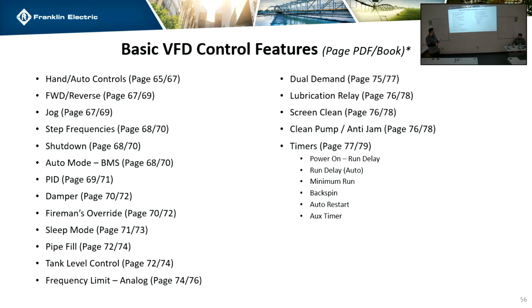73. If I heard that right, if the drive fails for whatever reason, instead of using the drive, it'll automatically change over to bypass. Yep. So if you don't trust the drive or you want it to be across the line, you can also have the drive, instead of running itself, just operate a contactor so that it throws it into bypass. But if you're in a, not that I'm just kind of trying to get an idea.